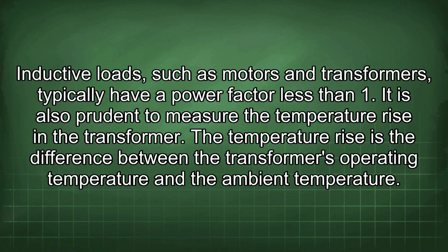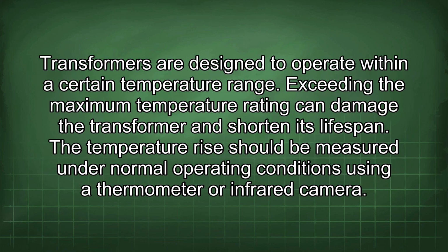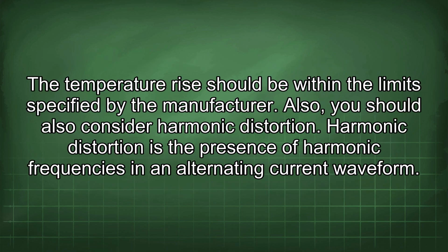It is also prudent to measure the temperature rise in the transformer. The temperature rise is the difference between the transformer's operating temperature and the ambient temperature. Transformers are designed to operate within a certain temperature range. Exceeding the maximum temperature rating can damage the transformer and shorten its lifespan. The temperature rise should be measured under normal operating conditions using a thermometer or infrared camera. The temperature rise should be within the limits specified by the manufacturer.